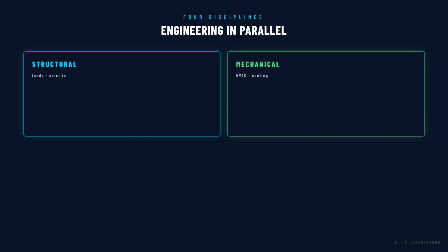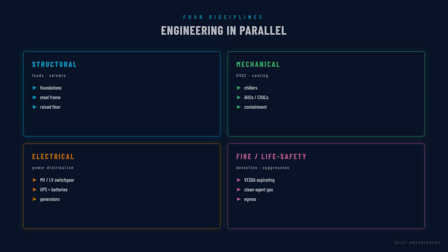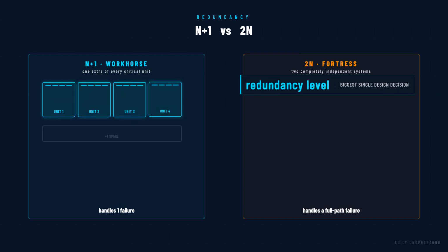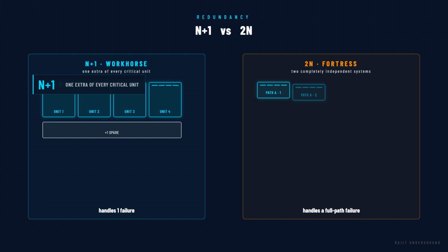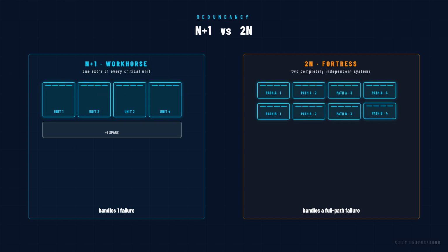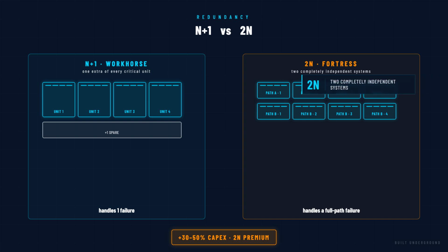The single biggest design decision is the redundancy level. An N+1 design means you have one extra of every critical component. If you need 4 cooling units to handle the heat load, you install 5. If one fails, the others cover it. A 2N design means you double everything. 2 completely independent power paths, 2 sets of cooling, 2 of every critical system. If an entire power feed fails, the second one takes over seamlessly.